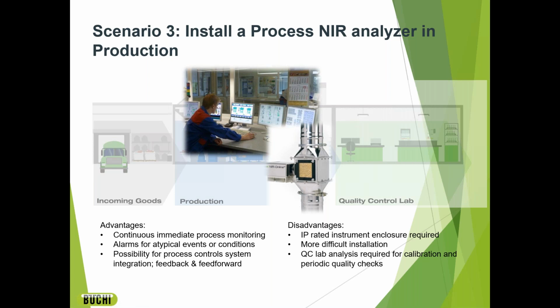Scenario 3: the instrument is installed directly in the production line. Rather than an operator going out to grab a sample, the product is continuously monitored, and information is fed back to a control room or other control station. The advantages: it's continuous, giving immediate process monitoring under all conditions. Alarms for atypical events or conditions are automatic, and there's the possibility for process control integration with feedback or feed-forward control systems.